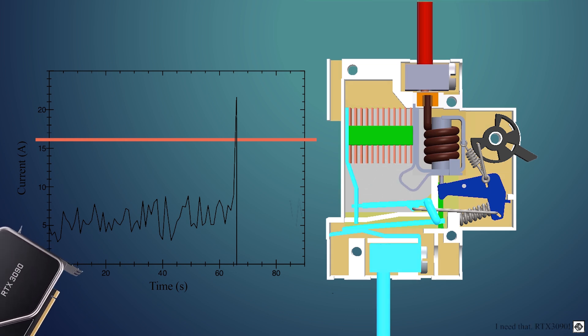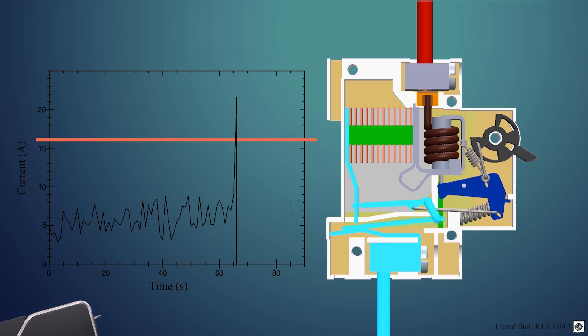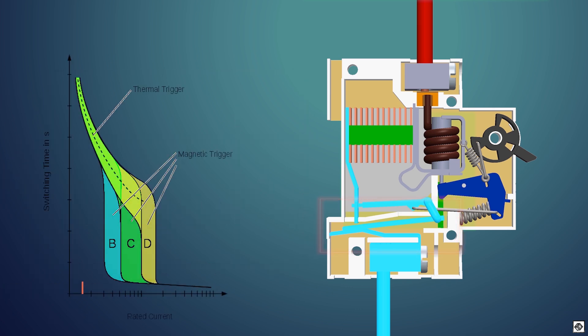And you may know that some appliances have power spikes where they can draw more current than their rated value. So we need a mechanism that takes time to trigger and won't trip the MCB during small spikes. Thus we have this bimetallic strip. This will trigger when a small overload is for a large amount of time or a large overload is for a small amount of time.